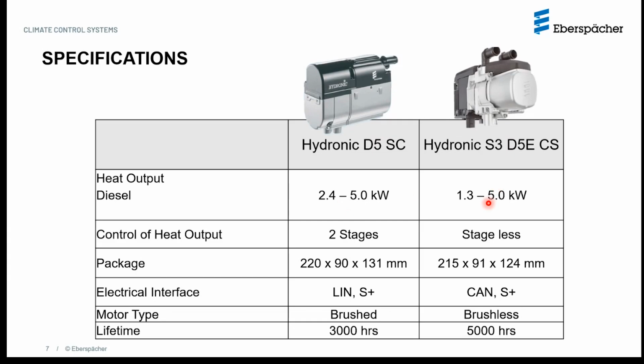So to minimize the chances or the risk of such failures, they have extended the operational range in terms of the minimum and maximum BTU. So thereby, the heater will have to make fewer restart attempts during the whole operation of the heater. The heater will operate between this range, but when the temperature of the coolant exceeds a certain threshold, it will switch off automatically and then automatically restart again. This is the routine operation of both the first generation and the third generation heaters. But in case of the third generation, the minimum output has been lowered so that the amount of times that the heater will have to switch off and then restart is basically less as compared to the previous generation.